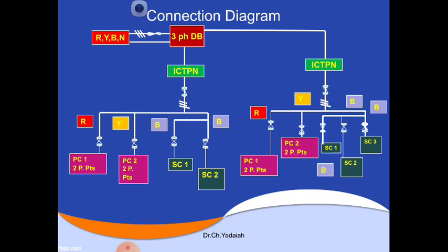But what will happen with the nature of the loads in AC? Suppose in the case of large capacity consumer loads, where there are refrigerators, air conditioners, small pump sets and motors. These are inductive loads. Once inductive loads are switched on, initially they draw 5 to 7 times the current as a starting current. Some inrush current may be of higher values. Due to the high starting current, it initially draws a large amount of current.